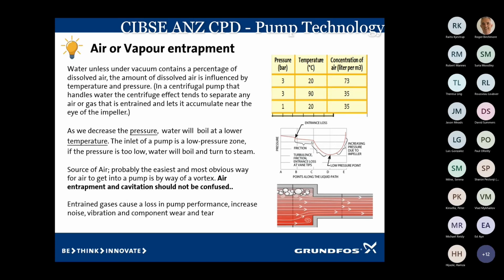The chart up here is a really good chart. It's from Spirovent, and you can see here that at 3 bar at 20 degrees, we've got 73 litres of air per cubic metre. If we lost our pressure tank, let's say it's a heating system, and our pressure tank in the basement, we lost that pressure to 1 bar, we've just given off 35 litres of air into our system.